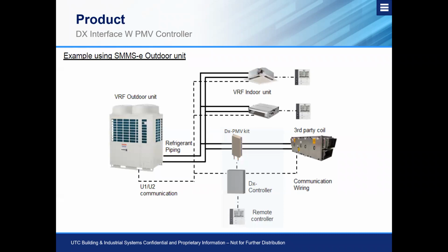So one unique advantage that we have with this Carrier system is what we call our DX Interface PMV controller. PMV stands for pulse motor valve, or electronic expansion valve. What we can do with the DX PMV kit is integrate into a third-party air handler with a custom third-party coil, utilizing this PMV kit for the refrigerant to fit into an existing air handler, while still being able to tie in other traditional VRF indoor units such as the cassette and ducted style unit that we see here in this depiction.